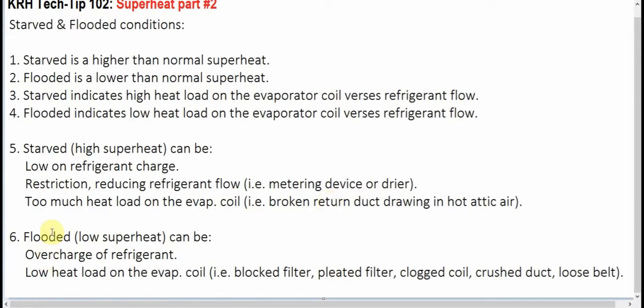The flooded condition, which is a low superheat, can be an overcharge of refrigerant, or it can be a low heat load on the evaporator coil. This is very common where we may have a blocked air filter, where the size of the filter really does not sufficiently allow airflow with a pleated type filter. So maybe they need to go to a fiberglass filter, the typical throwaway furnace filter that will allow more airflow. Or a clogged coil. It could be that the unit was run without the filter for a while and the coil got clogged. It could be a crushed duct, a crushed supply or return duct.